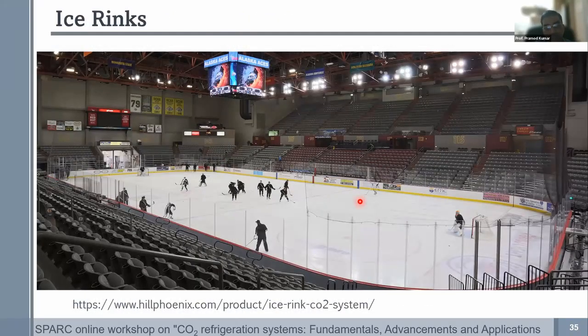This application, which we will not see in India, is worthwhile mentioning: ice rinks, where the entire field is frozen with ice. This is a very nice application where CO2 perfectly fits the bill, because you need low temperature cooling to maintain the ice. As you keep moving, the friction between the ice skates and the ice sheet is going to cause the ice sheet to melt off, so you really need to keep it cold so that it remains as ice.